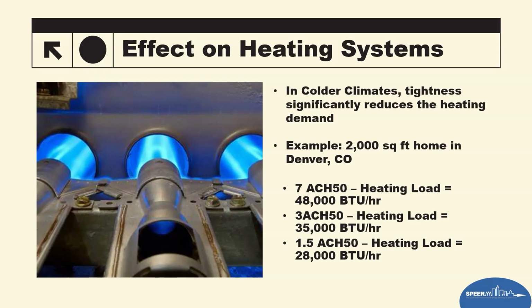But the difference could be looking at colder climates, and the same thing, a 2,000 square foot home. This one's in Denver. If it's 7 ACH, you're looking at 4 tons of heating. If it's 3 ACH, you're looking at just around 3 tons of heating. And then, of course, if you have a 1.5 ACH super tight high performance building, you're looking at closer to 2 tons. So that's, again, shrinking it down. But that's the difference of possibly installing an 80,000 BTU furnace, which we see a lot in Texas, or 70,000, down to a 60 or a 45,000 BTU furnace. But also smaller duct systems as well, and smaller trunk runs.